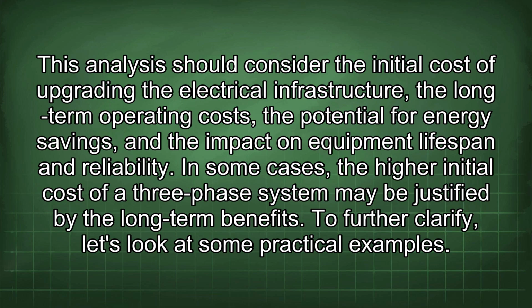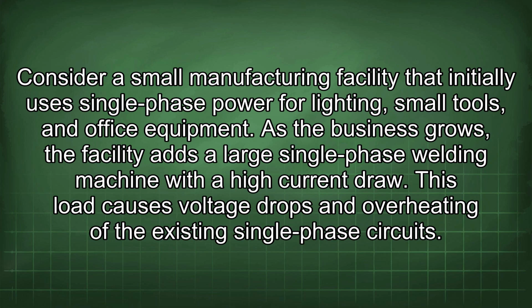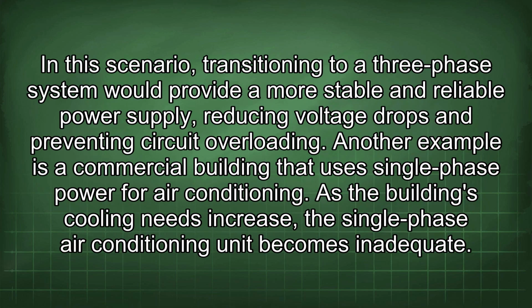To further clarify, let's look at some practical examples. Consider a small manufacturing facility that initially uses single-phase power for lighting, small tools, and office equipment. As the business grows, the facility adds a large single-phase welding machine with a high current draw. This load causes voltage drops and overheating of the existing single-phase circuits.